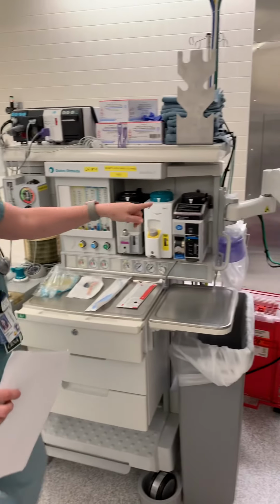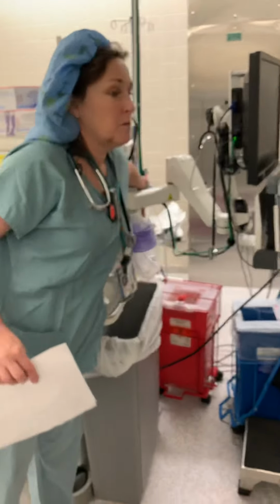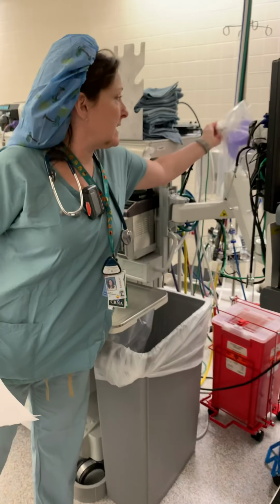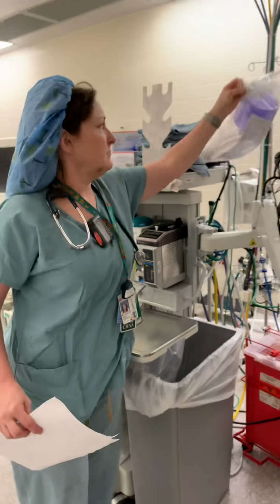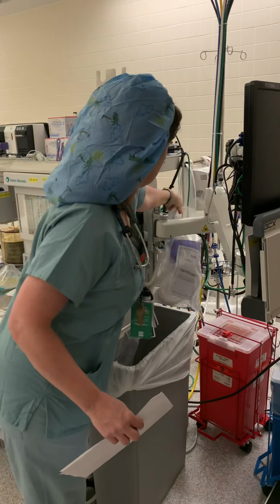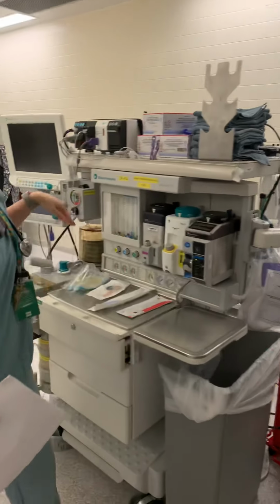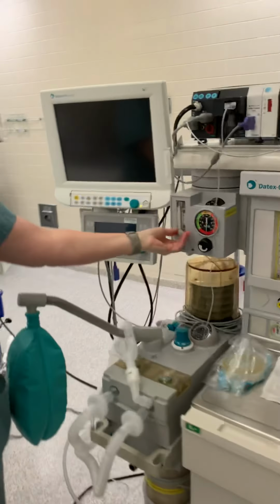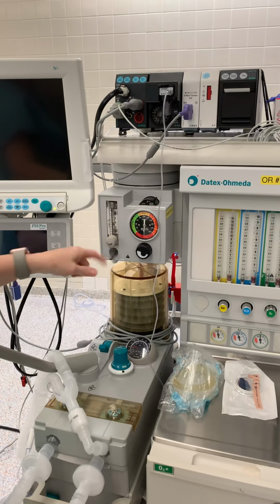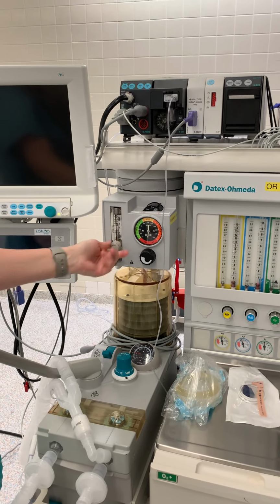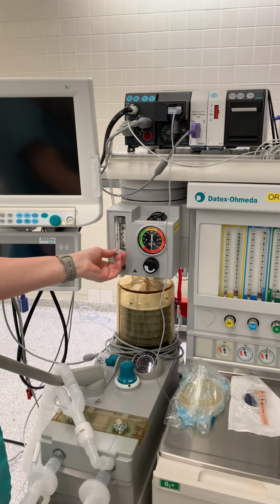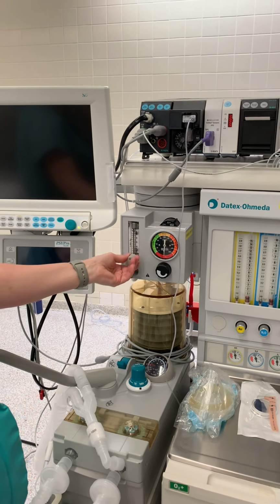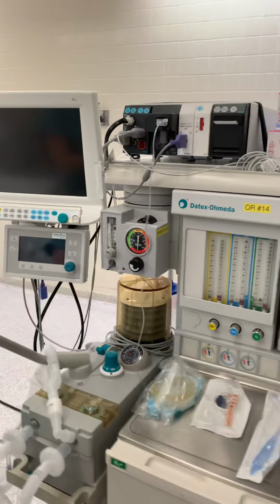And to do that, you will need an ambu bag, which is located on the back of your machine, back here. And you will also need an oxygen flow meter to attach that to, and you want to make sure that that's functioning properly. And you can see that our ball bearing goes up and down, and so we know that that works. So number one is checked off.